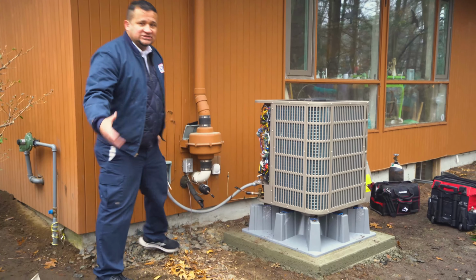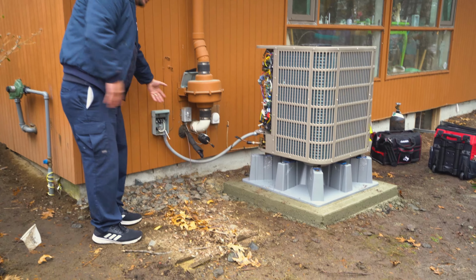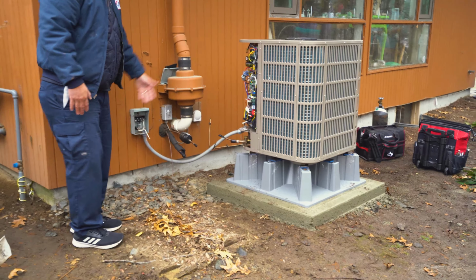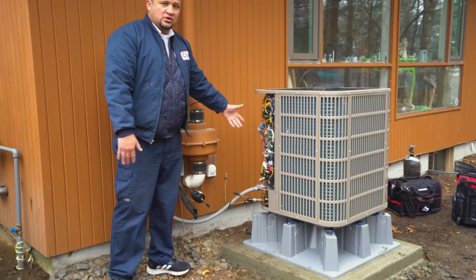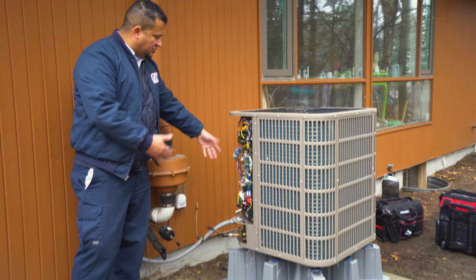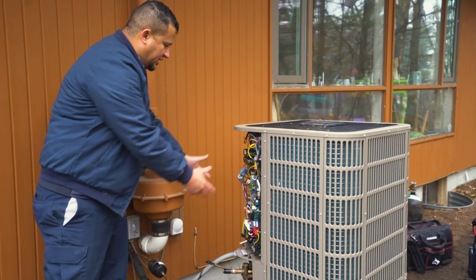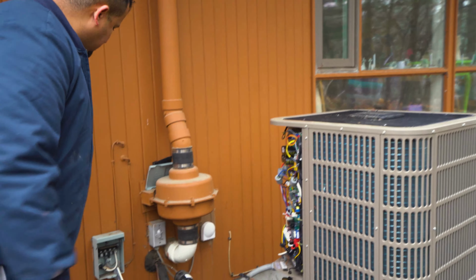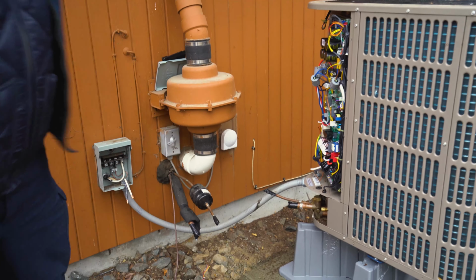So that's 2 violations that we found. The unit was right here, right behind the disconnect, and it also had no room to work on it. So what we did was simply move the unit in here so we have space to work on it, and also if you need to turn off the unit, we can come in here and just disconnect it.